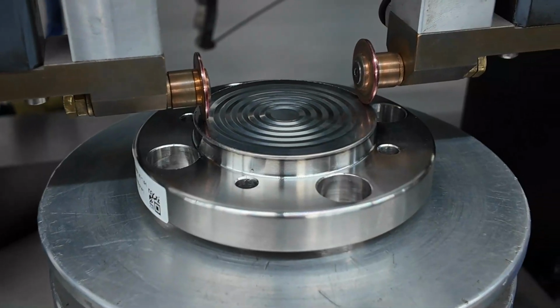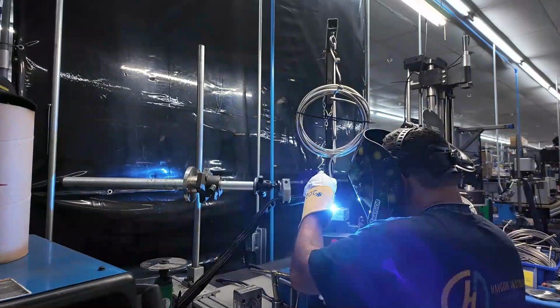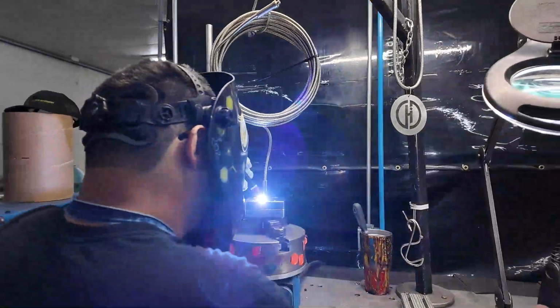When we weld those diaphragms onto the uppers, we fusion weld them with our TIG welder at the end. We also have resistance welding, or seam welding, right here—it's state of the art. There are two primary advantages to using resistance welding when attaching diaphragms to uppers. One, it's faster, and it produces a superior weld that allows us to join dissimilar metals. TIG typically doesn't like that, so resistance welding provides a very strong, sound weld when we're using dissimilar metals. Those are the two advantages of our diaphragm seal welding.